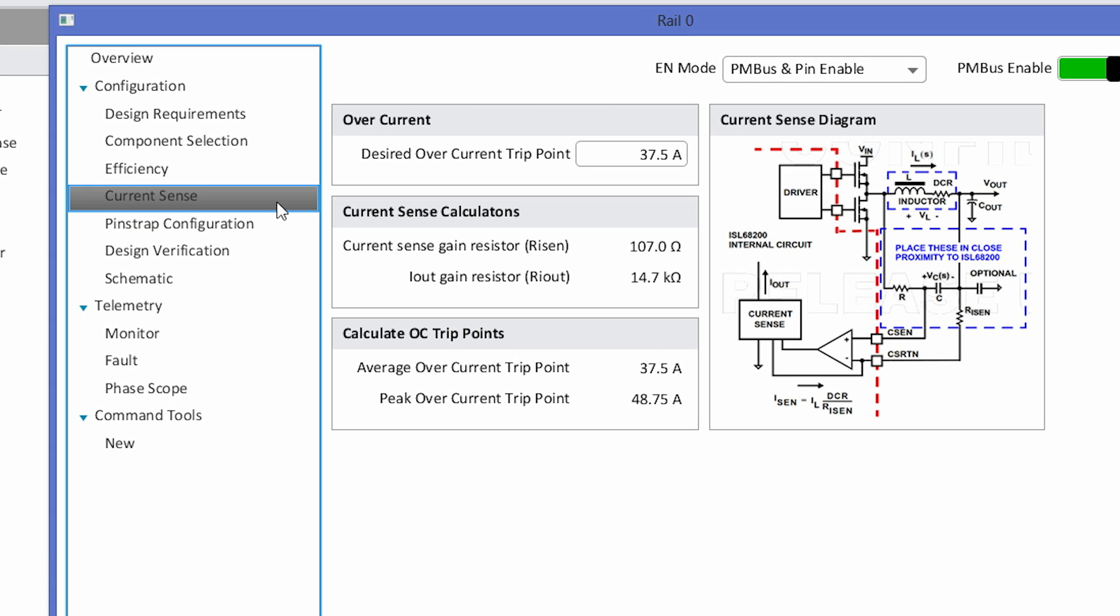The next page walks you through the overcurrent settings for the device. In this case, we have a desired overcurrent trip point of 37.5 amps. PowerNavigator automatically calculates the correct resistor values to use to set this overcurrent trip point, as displayed here.